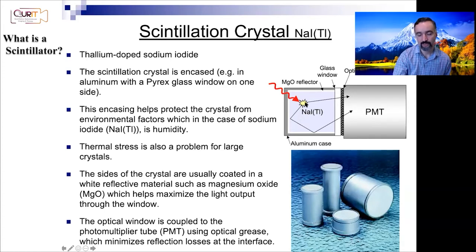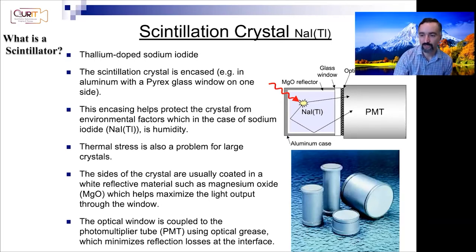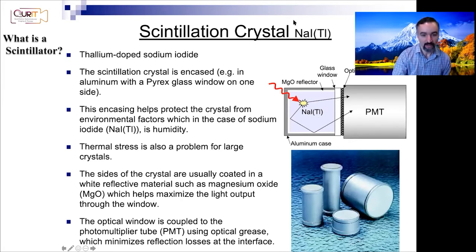The idea is that as scintillation photons are generated, you really want them all to move in one direction and end up being detected in the PMT — the photomultiplier tube — which will amplify the signal and convert it from light to an electrical signal for our system to process. This reflective material helps guide the generated photons in that direction. The optical window here is coupled to the photomultiplier tube using optical grease.